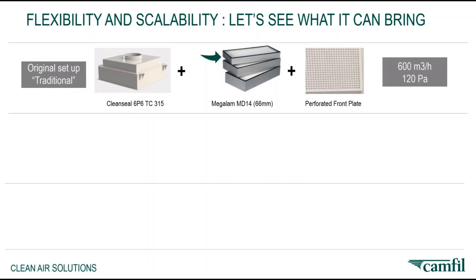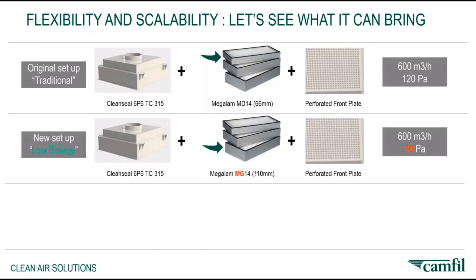So let's see how, from this configuration, we can make significant changes with the same housing. So now the energy manager is asking you to reduce energy consumption by X%. So this is what we will call the low energy setup. With the same housing, using a new filter, 110 millimeter, for example, and the same front plate, we have now saved 50 Pascal per housing.